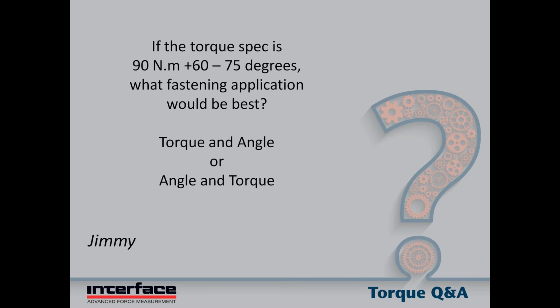But in any case, we could measure that using several of our sensors or sensor-instrument combinations that have torque measurement and then degree measurement as separate channels. So you can measure torque and angle separately but simultaneously, and you could achieve any combination of Newton meters and angle. That would be a manual system, though. We're using a torque transducer to monitor both the torque and the angle as the torque is applied. The question leads me to believe that there are other systems in the market that have certain modes for measuring this. Maybe they're automated, or they do some kind of analysis of the data, and maybe there's a torque and angle or angle and torque mode or different equipment. But we sell basically the components for measuring torque, and then instrumentation that measures torque and maybe logs it or displays it as a graph along with angle and whatnot.